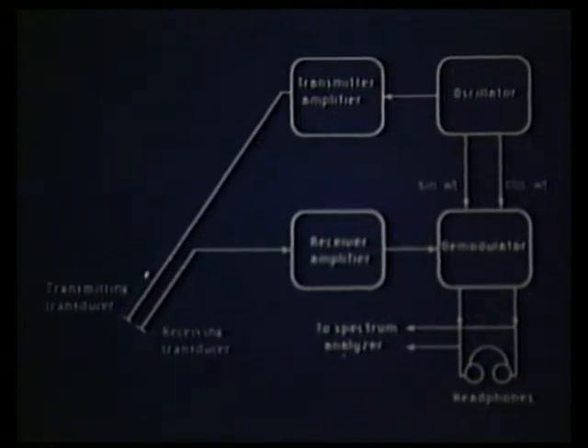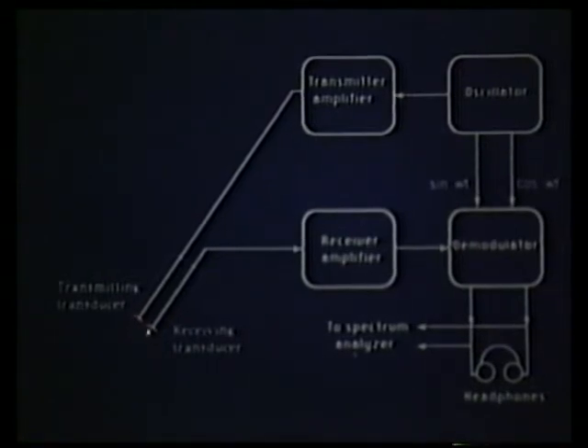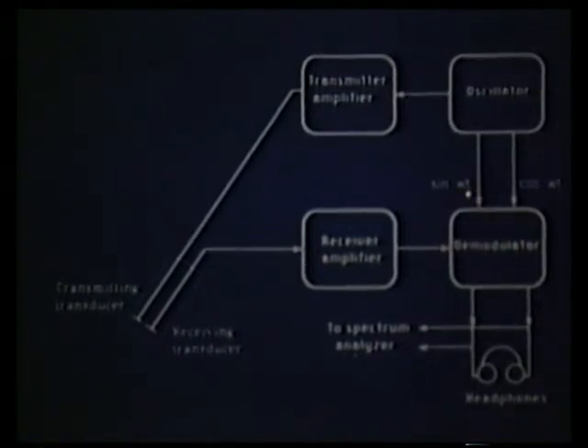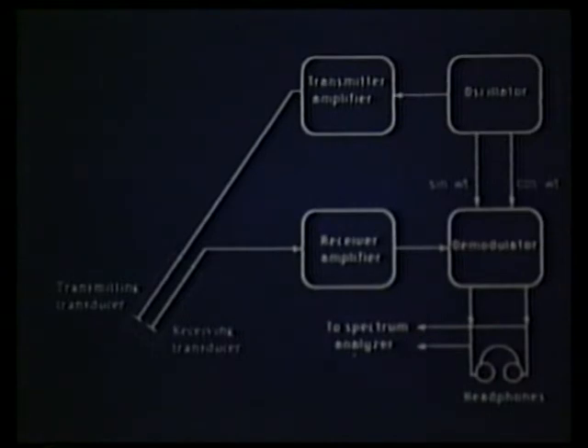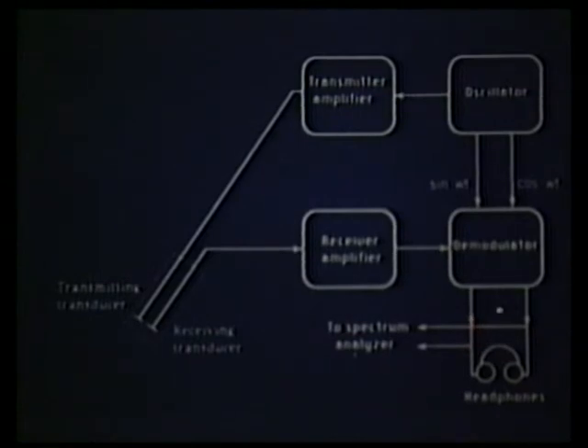The signal produced by the oscillator is transmitted to the transmitting ceramics. The received signal is amplified and then sent to a demodulator, where it is compared with two signals in quadrature in order to detect the positive or negative value — that is, the sign of the Doppler frequency shift.